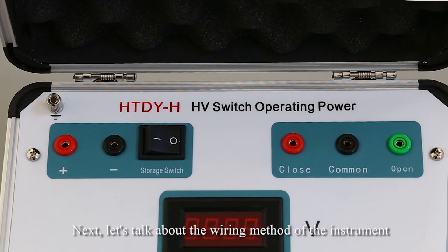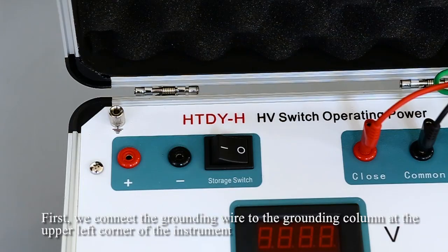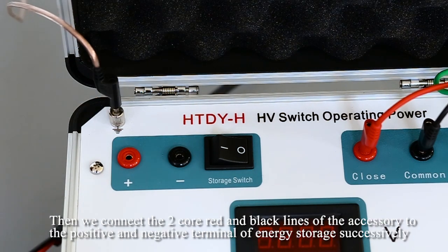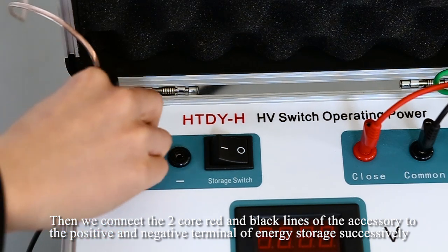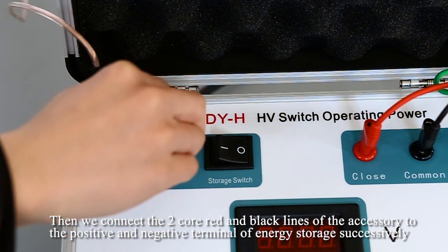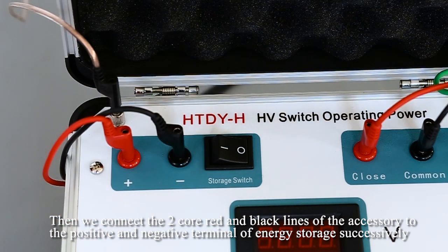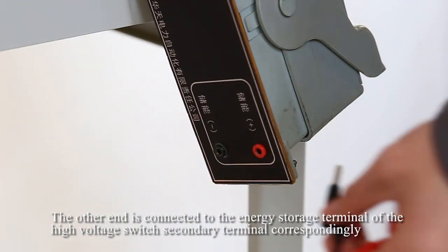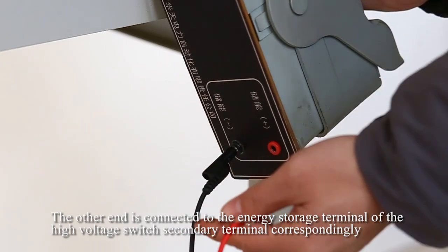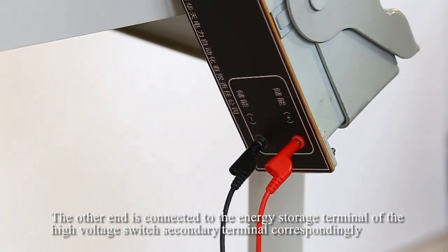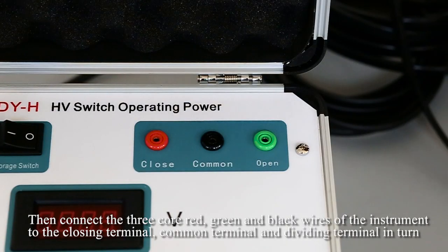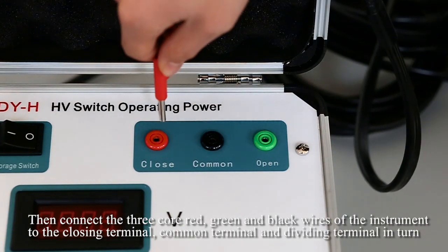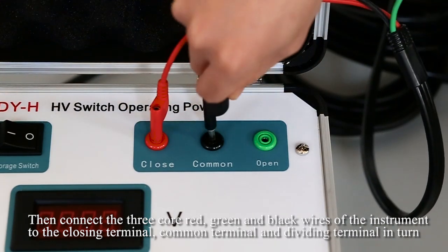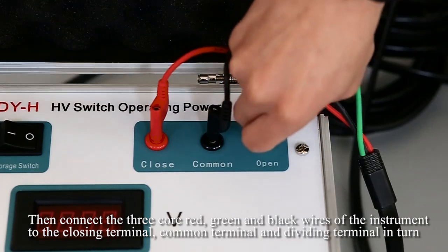Next, let's talk about the wiring method of the instrument. First, we connect the grounding wire to the grounding column at the upper left corner of the instrument. Then, we connect the two-core red and black lines to the positive and negative terminals of energy storage in turn. The other end is connected to the energy storage terminal of the high voltage switch secondary terminal correspondingly. Then, connect the three-core red, green, and black wires of the instrument to the closing terminal, tripping terminal, and the common terminal in turn.